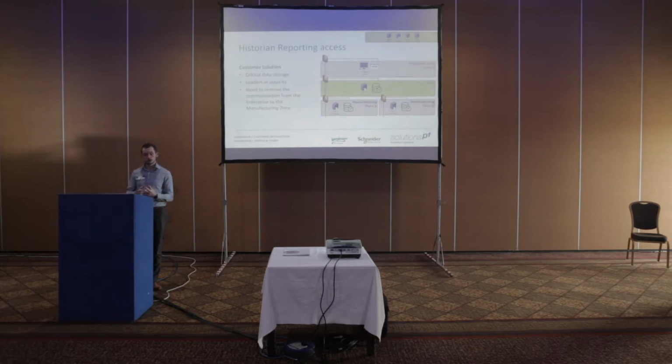So what we did was introduce a tier 2 Wonderware historian at that demilitarized zone layer. The idea then is that we're now pushing data from those manufacturing zones up to that centralized layer, and then our enterprise zones are just accessing that demilitarized zone layer, or even further out if we wanted it to. But again, it's key that we use that centralized environment.